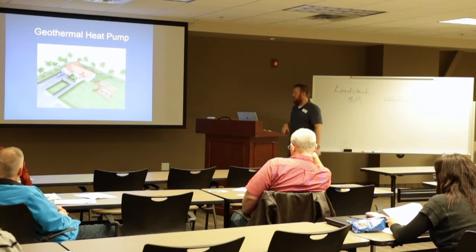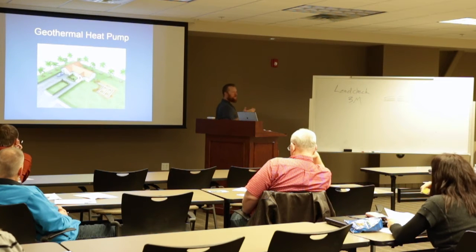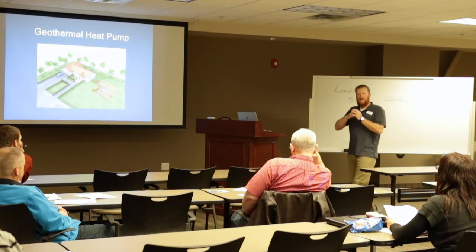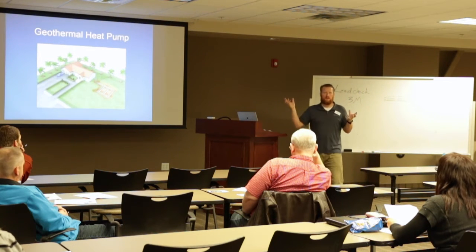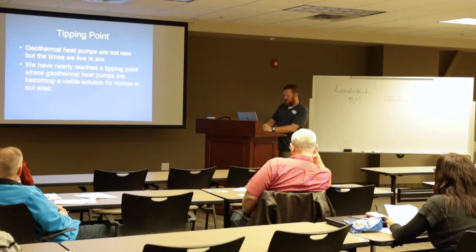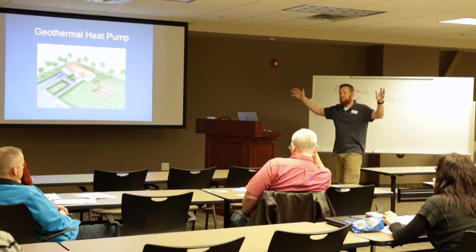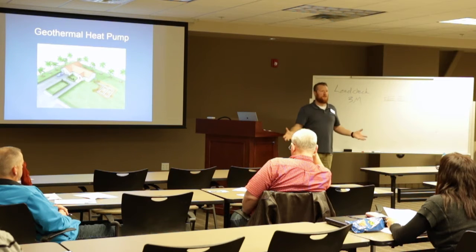If you dig down into the earth, there's a pretty common rule of thumb. The temperature of the soil 10 feet below the surface will be equivalent to the average temperature annually. In Provo, I think it was last year, I've got a slide on here somewhere, the average temperature was like 53 degrees. So if you took all the highs and lows, what's the average temperature annually? It's low 50s. You dig down 10 feet in the soil, it's low 50s.